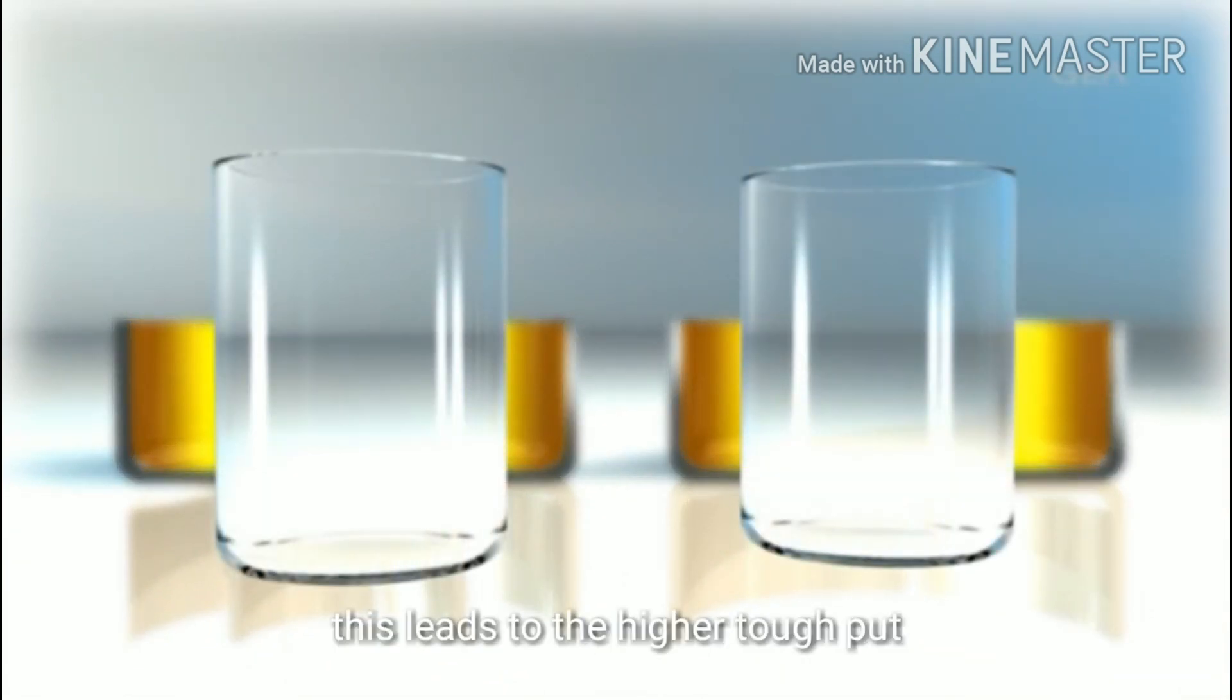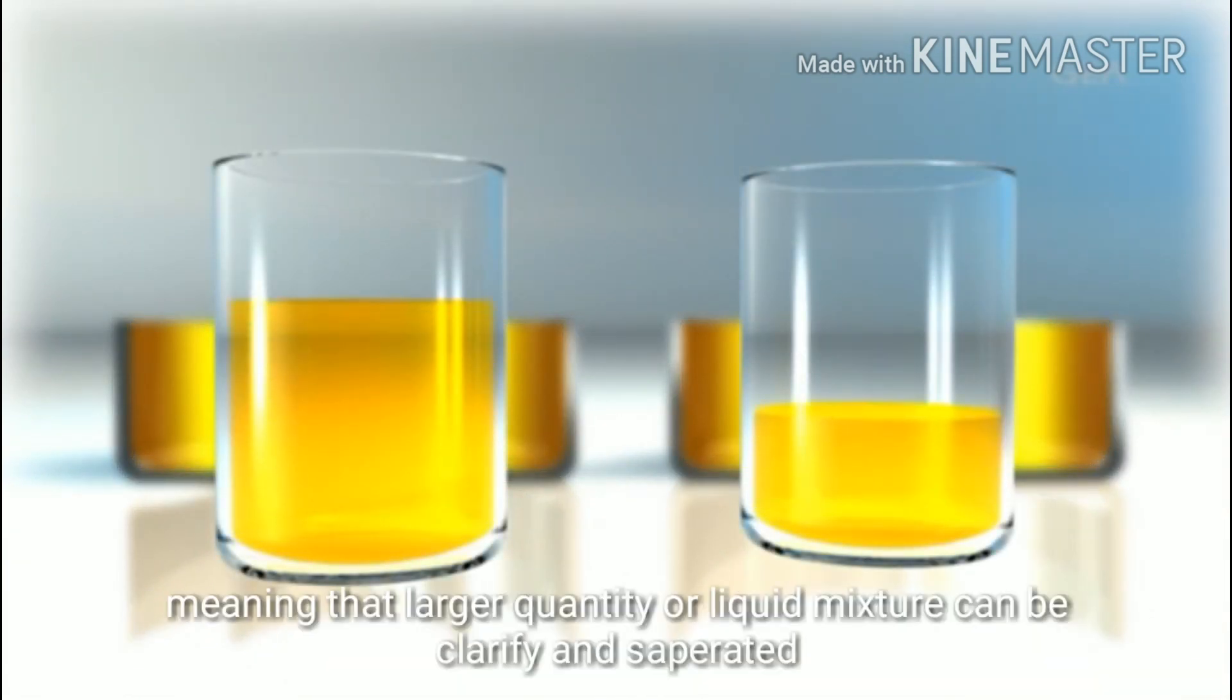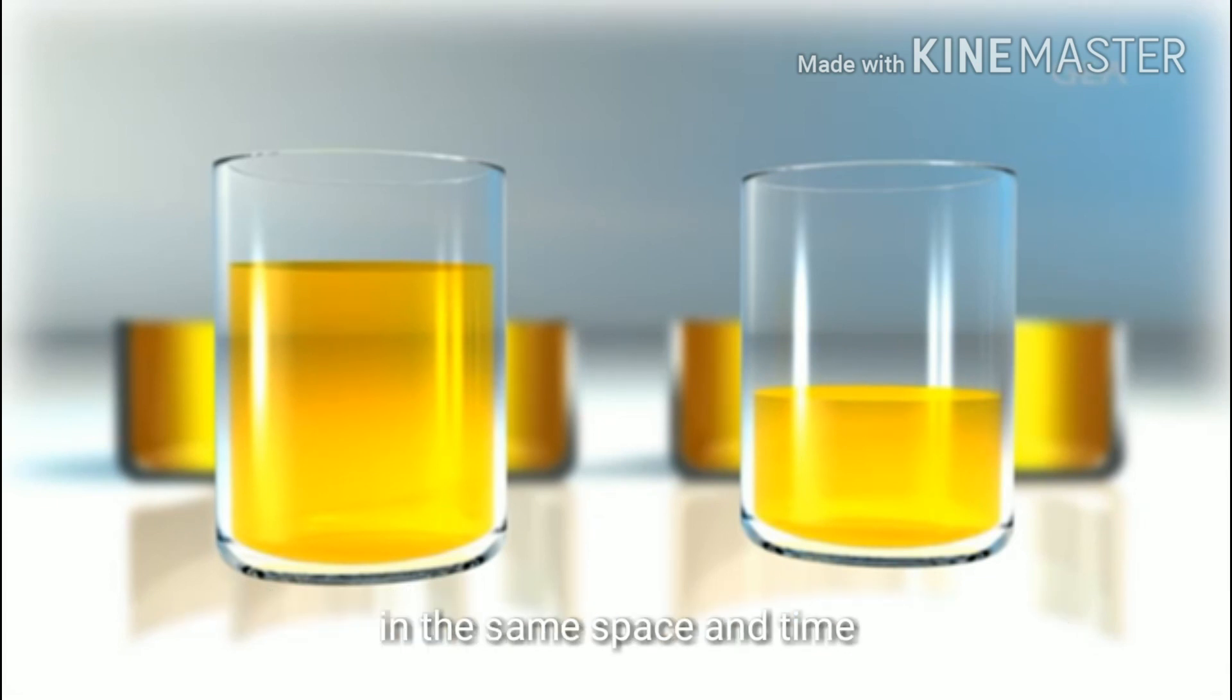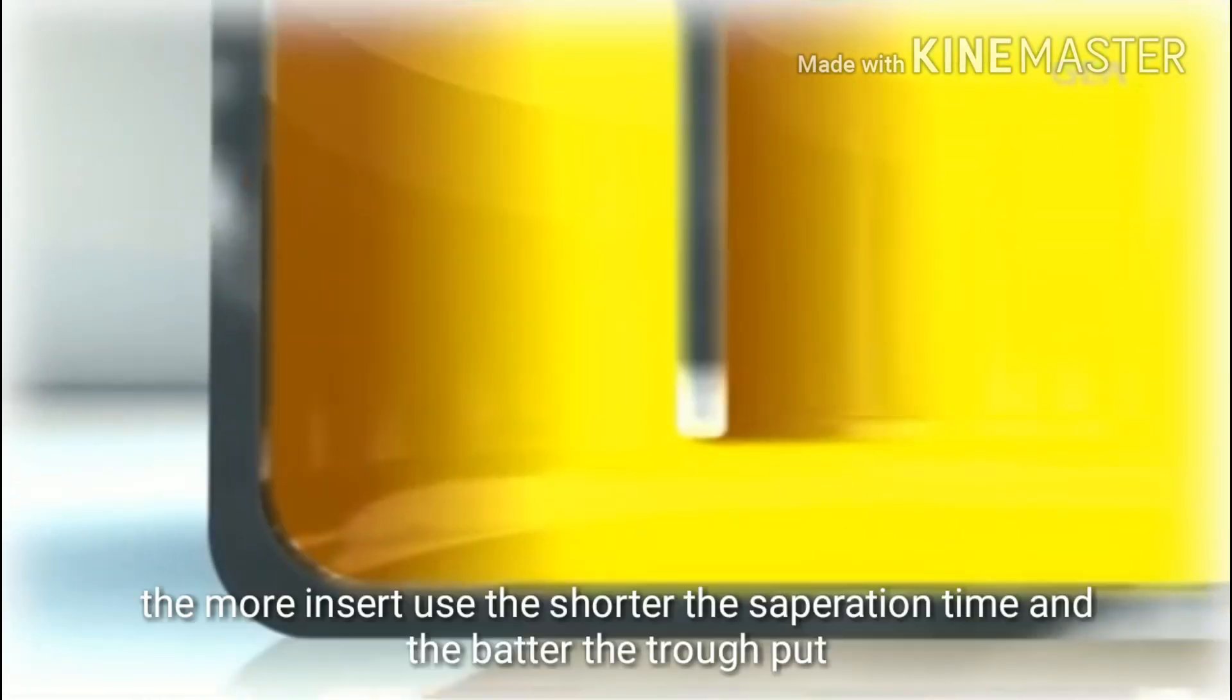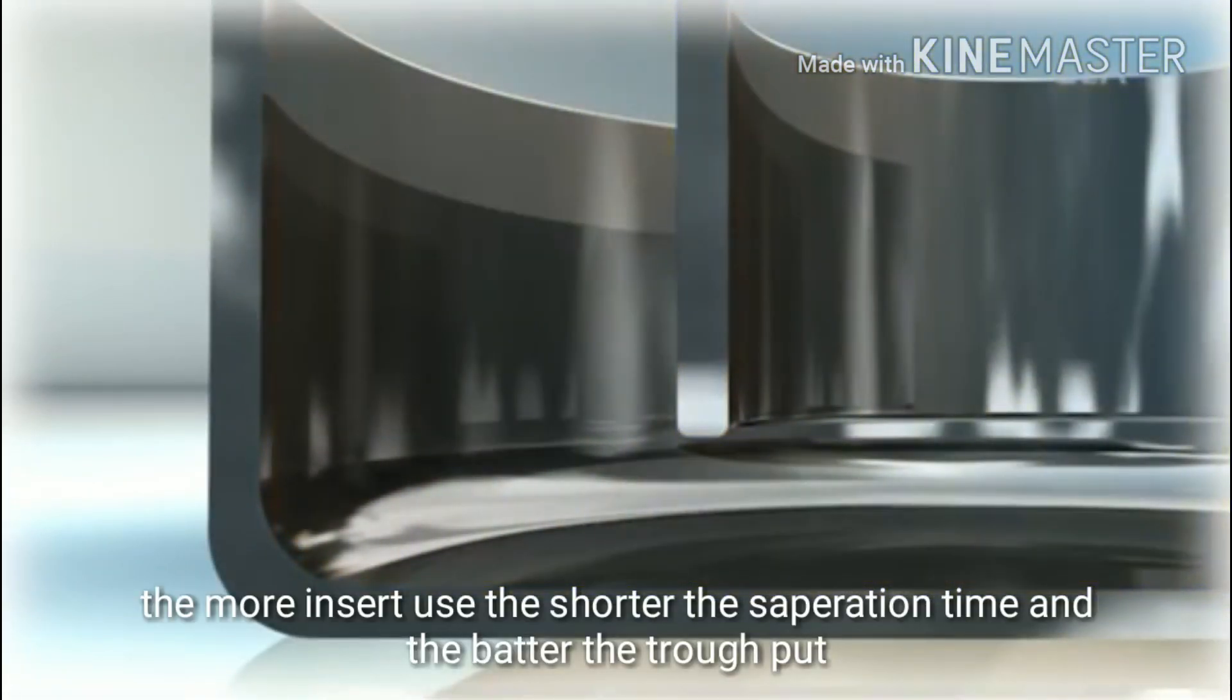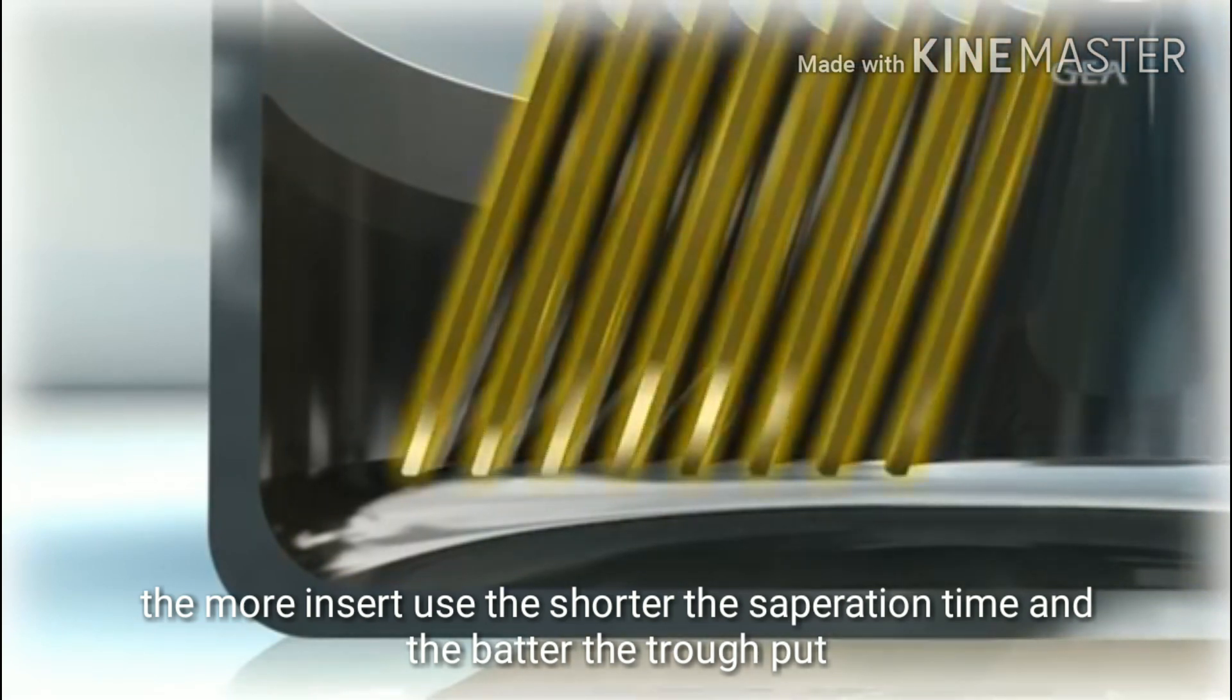This leads to a higher throughput, meaning that larger quantities of liquid mixtures can be clarified or separated in the same space of time. The more inserts used, the shorter the separation time and the better the throughput.